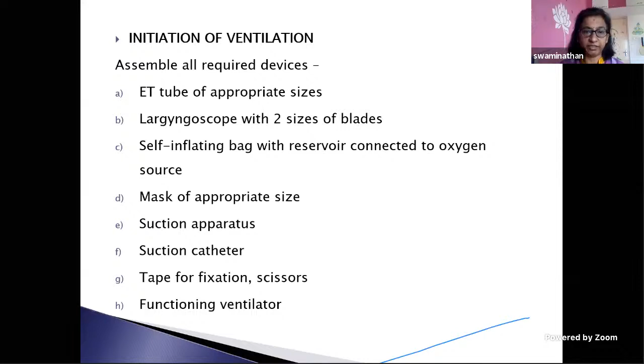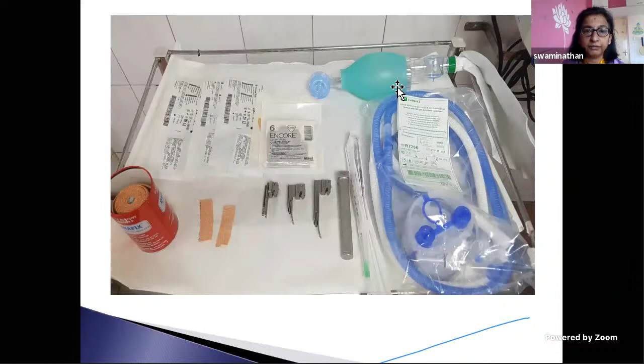Time and again, when we go to the labor room, they may even give us a suction apparatus used during the labor and all that, where very high pressures are used, which can injure the mucosa and cause undue damage. So for the suction apparatus, the manometric pressure should be monitored well, at or below 100. And of course, once tubed, tape for fixation, scissors, everything should be kept ready, and the functioning ventilator should also be ready. So yes, this is the equipment check. All the larynx blades, the suction catheters, the ventilator tubing, ambu bags, the plaster, everything.